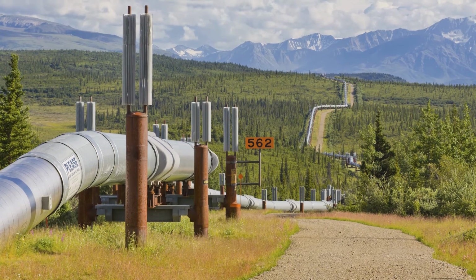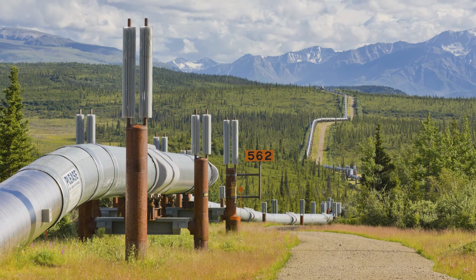Industrial equipment is deployed with the expectation it lasts a decade or more, so it's really important to deploy the latest available technology at the time that you put it out there. And in that case, it just makes sense to use LTE. It also offers great bandwidth, but in these applications like SCADA, where you're sending maybe 100 or 200 bytes, the biggest advantage is the latency. You get very fast responses to your polls. If you're deploying in an area where you don't have LTE coverage yet, you can put LTE devices out, they'll run on 2 or 3G right now, and when the coverage gets there, they'll switch over and run on LTE.